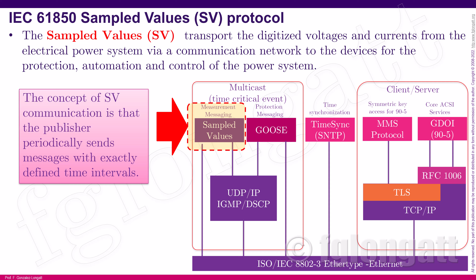Somebody asked me how we simulate the data network. In reality, with real time, we are not simulating — we are generating the data streams. Here we test a relay, ABB REF 615, and in this relay we can send signals using the IEC 61850 protocol. In real life, these signals must come from the digital CT or digital VT, the voltage transformer, current transformer, or merging unit.